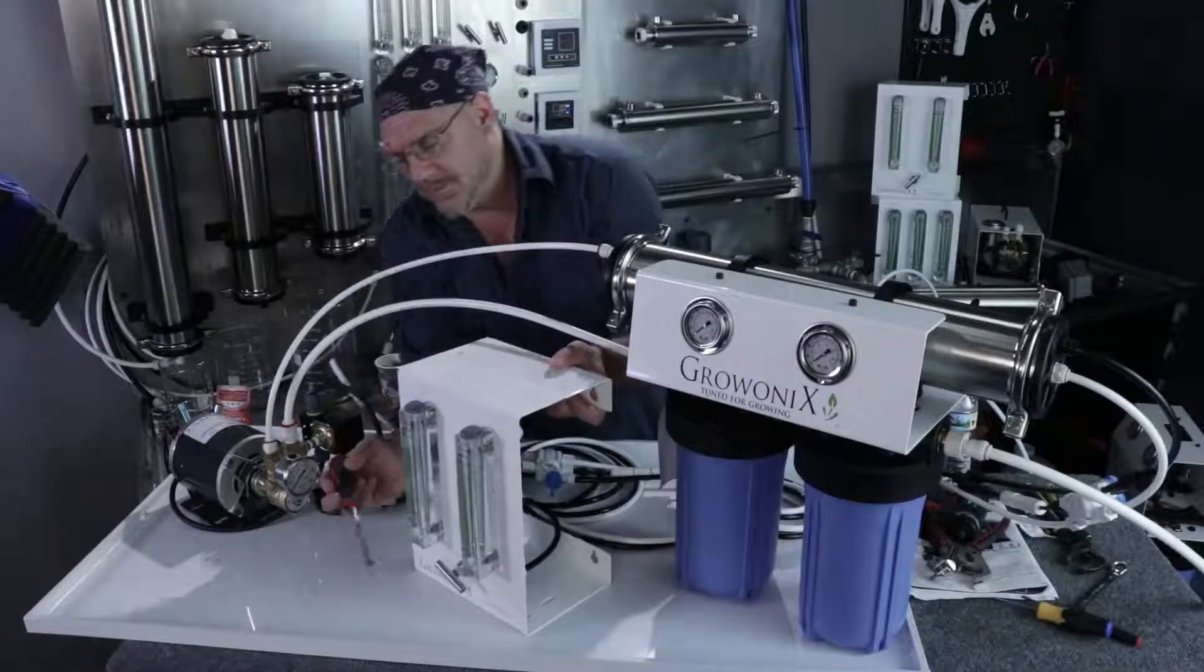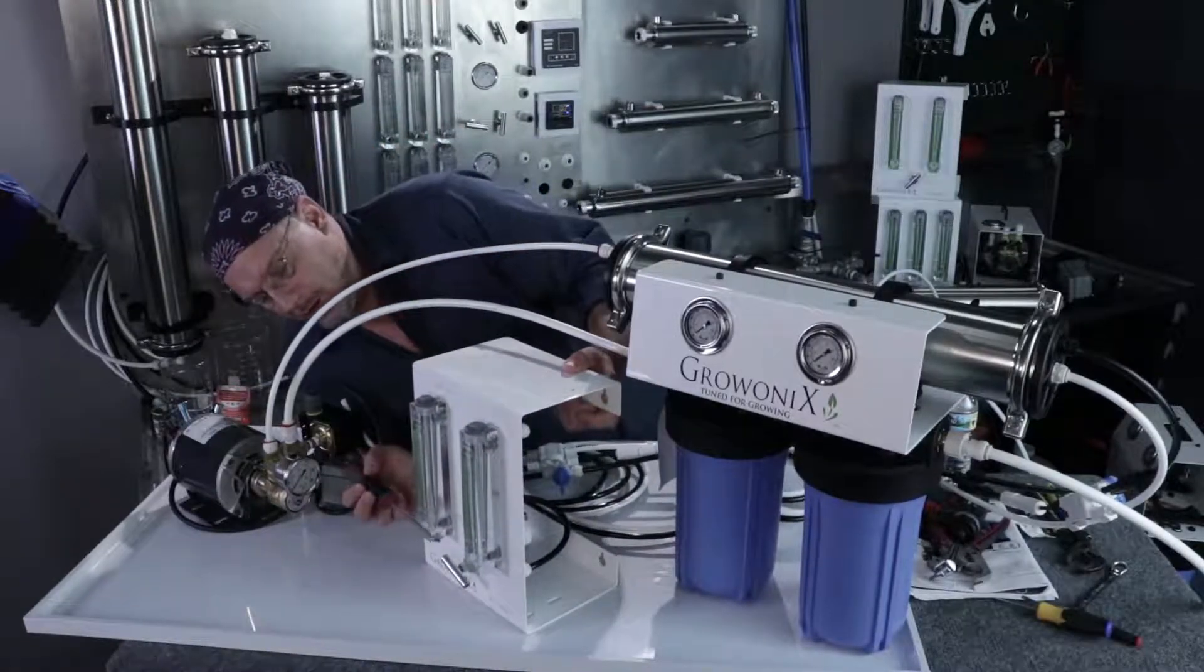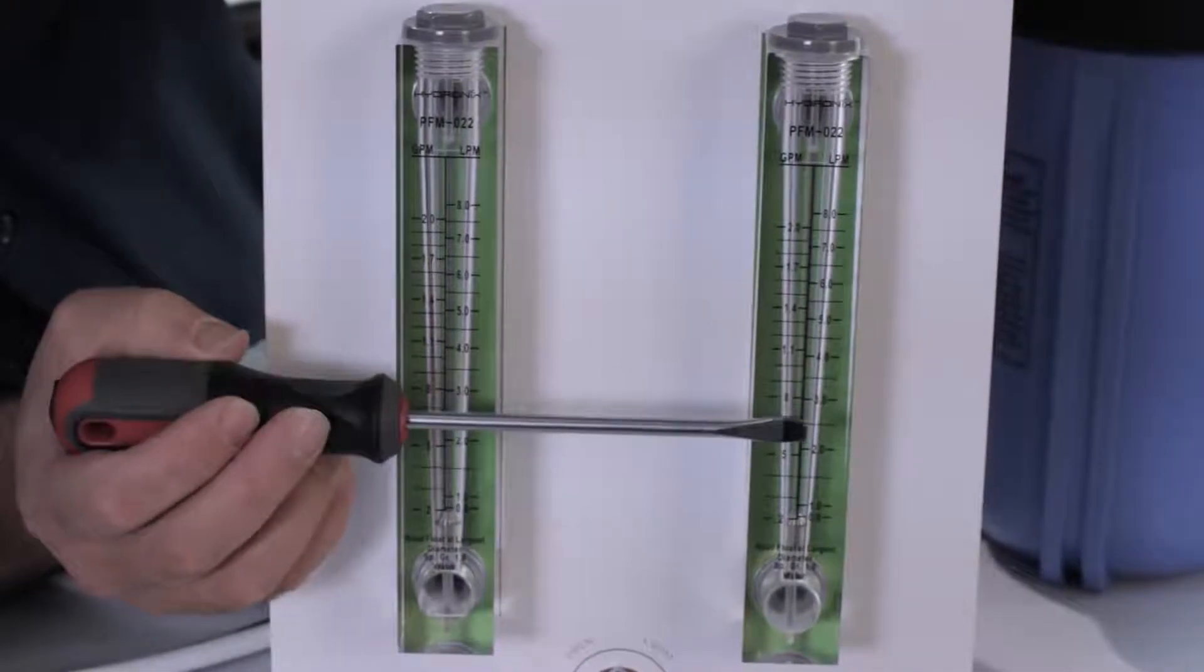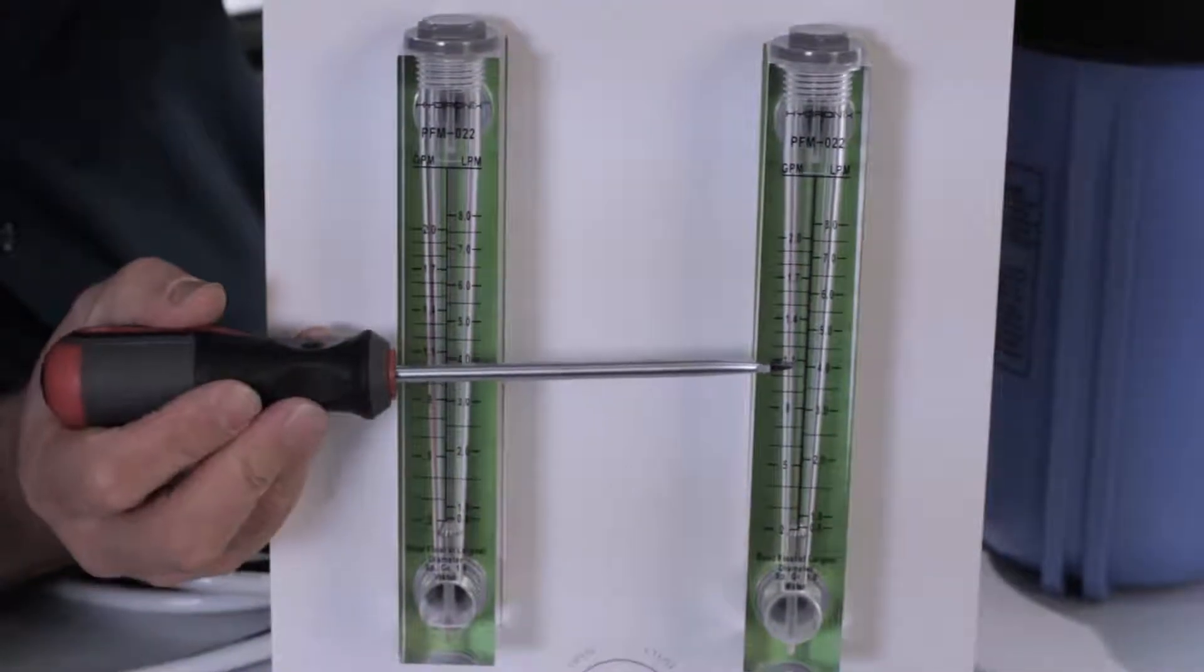On a Flowbox, when the drain water equals the amount of feed water, then you're at one-to-one. That's the system ratio.